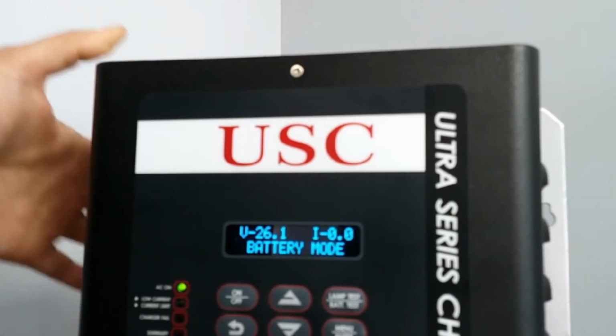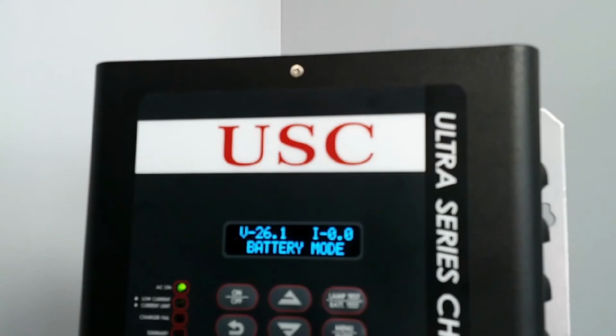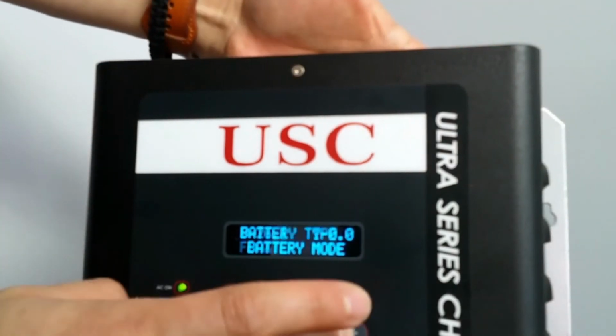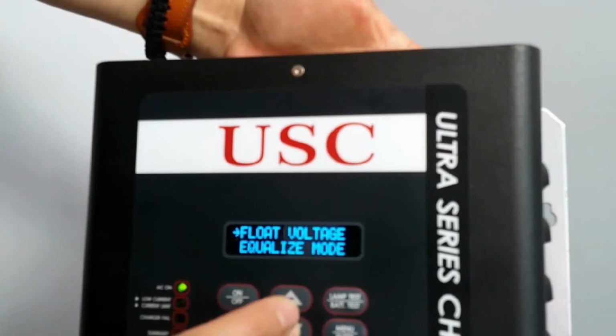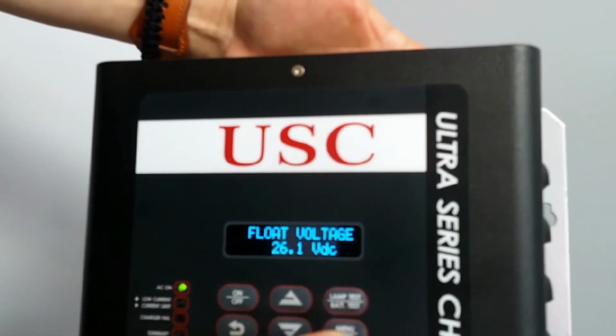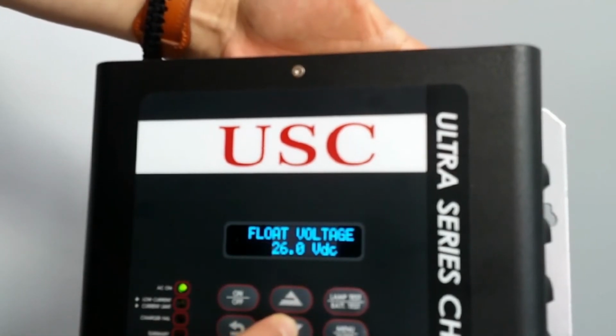So you saw that it changed from 25 volts all the way to a 26 volt setting, which are different adjustment ranges that are set as default from the factory. But going a step further, you can also see how easy it is to adjust your float voltage setting up and down. So you had it set at 26.1 and can easily go down to, for example, a 25 volt level.